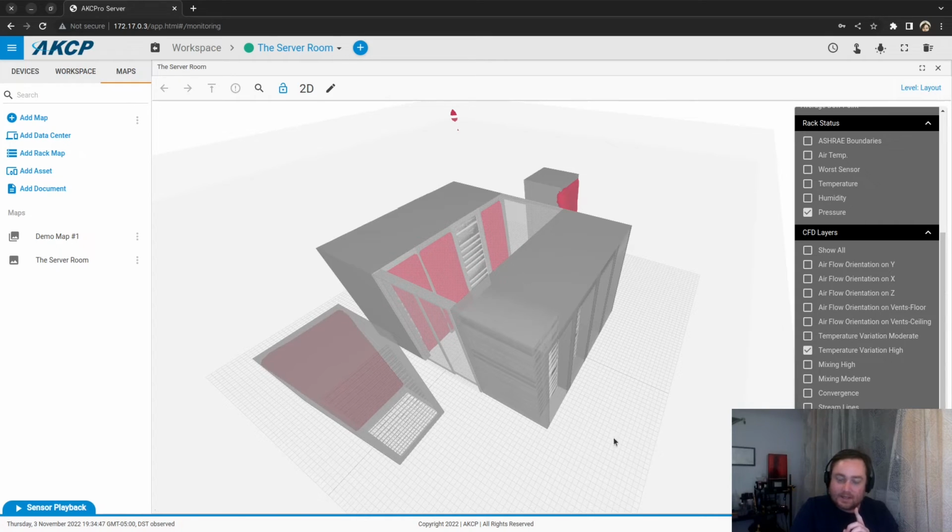So note the difference. This model is like the first one, closed, but with the data of the second one, open. So if someone uses the probe in reality, puts the sensor on the rack, draws something like that and gets a result like that, we know that it's not reality. And if you look at the temperature of the probe, you will see the difference. And you see, hey, I have a mixing. That's why my model is blowing up. My model is saying something is wrong. And that's the clever thing. Because like that, you know that you have something wrong with your drawing, something you drew by sensibility, you drew what you think exists, but it's not the reality.